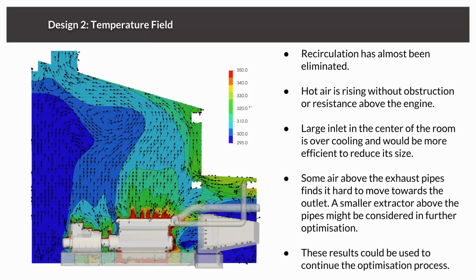We have some air that is being directly moved towards the outlet. The cold air on the very left side of the image, there's a big tile that was the inlet itself, and it's directly going to the outlet. We could optimize this design by moving it somewhere else.